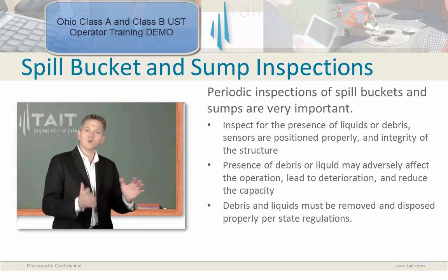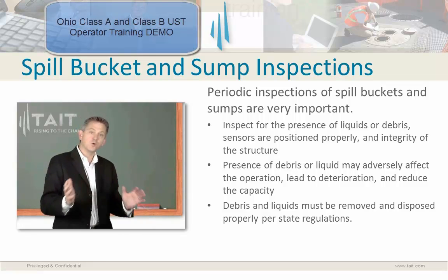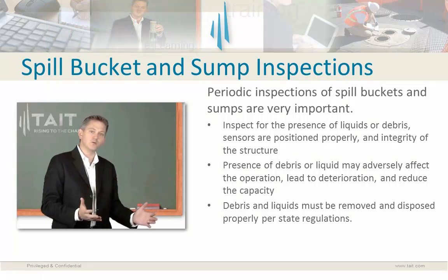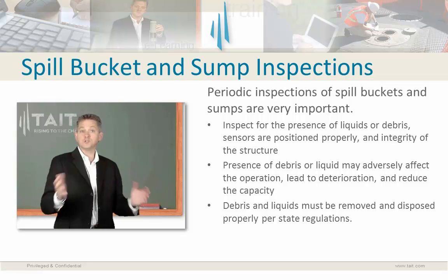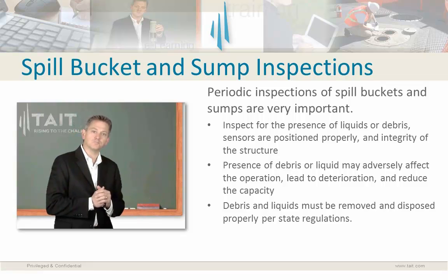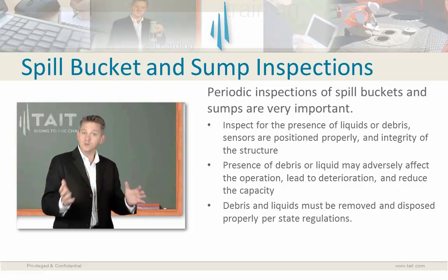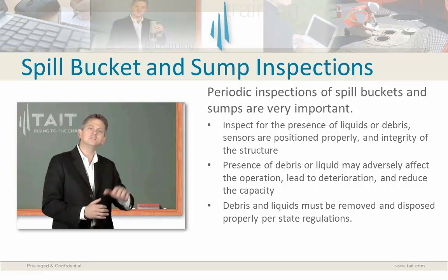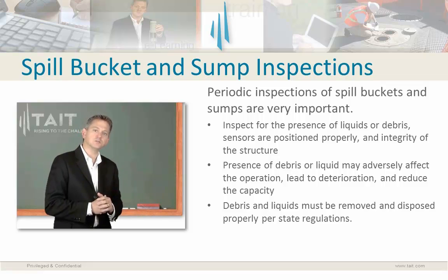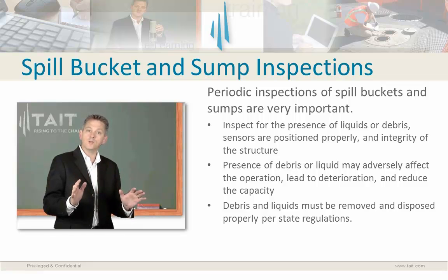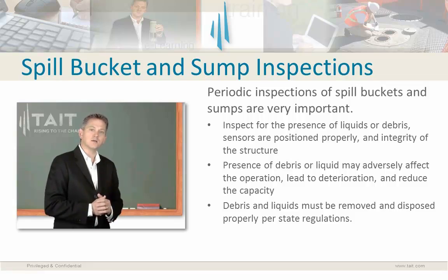If there is liquid or debris in a sump or a spill bucket, that can adversely affect its operation, lead to deterioration, and/or reduce the capacity of that structure. Now, if liquid or debris is found inside of these structures, it needs to be properly disposed of per state regulations. Additionally, state requirements for inspection of these structures can be found on this slide.